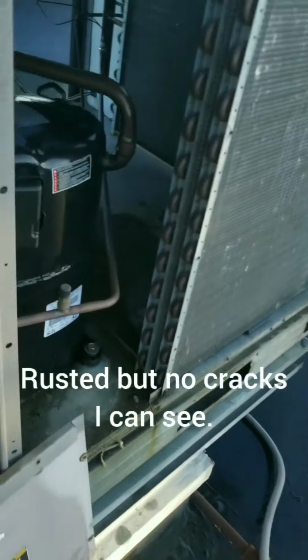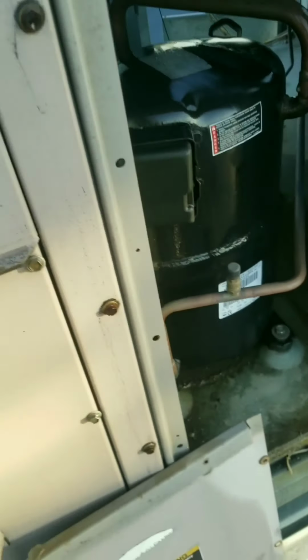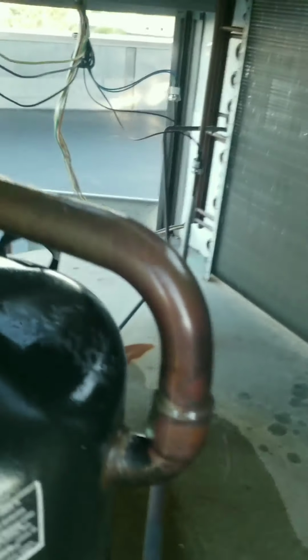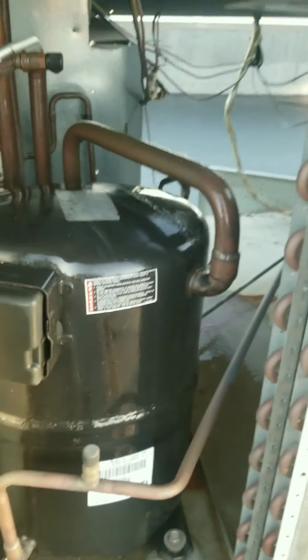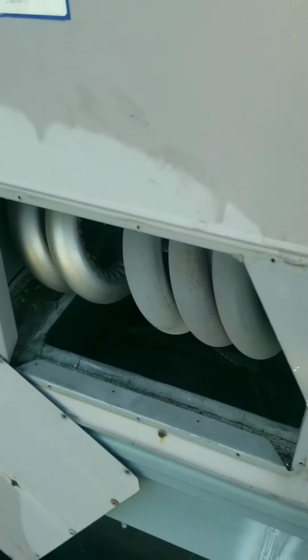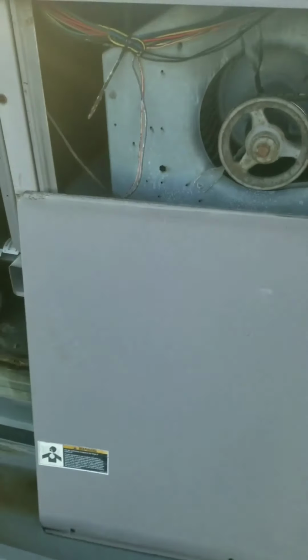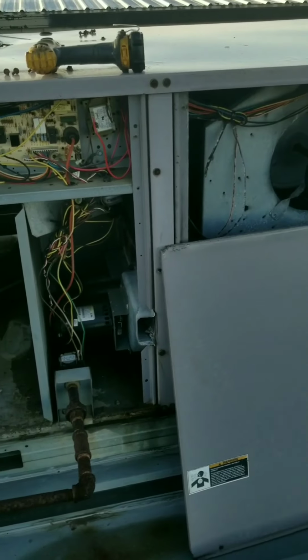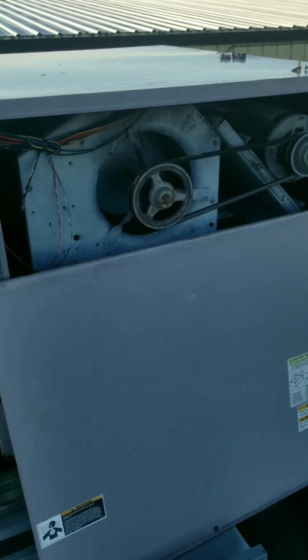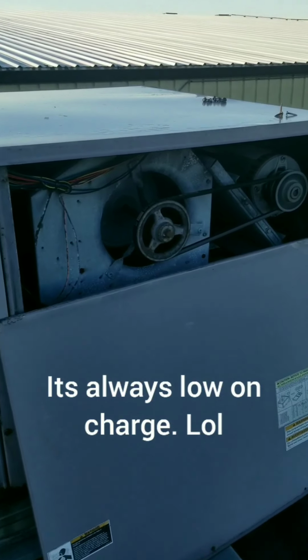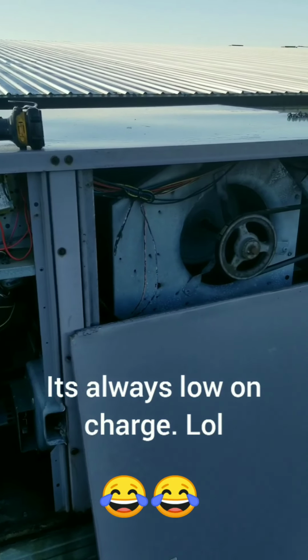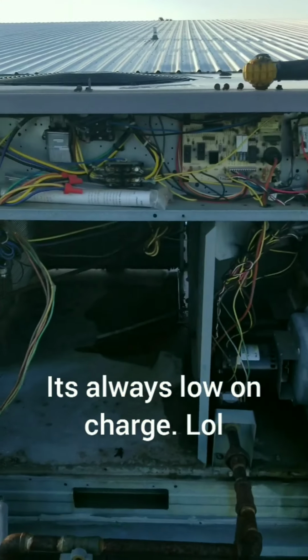Anyways, let's see. Filter's dirty. Seen worse. Looks like they were changed in 2019. So other than our blower motor, looks like it's running. Their maintenance guy said they thought it was low on charge, as always. It's always low on charge until the blower motor doesn't run, and he said it would kick on, kick off, kick on, kick off. Well, it's probably true when the blower's not running. So let's dig into our blower relay, blower motor, and see what's going on there.